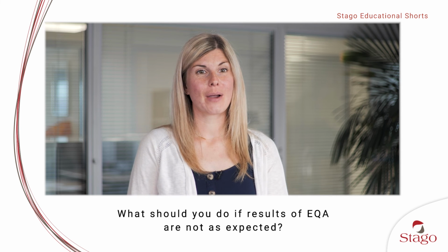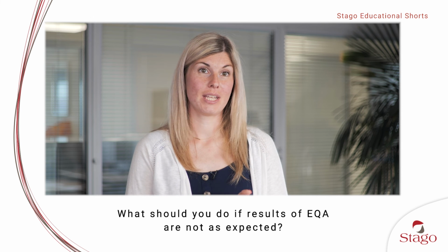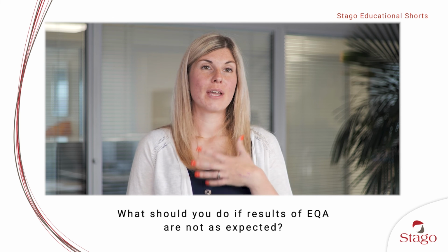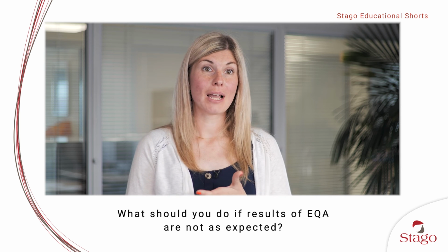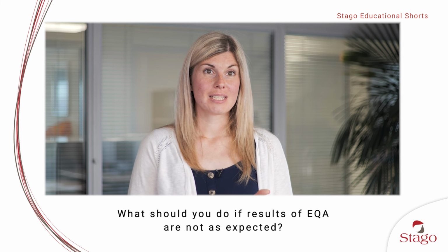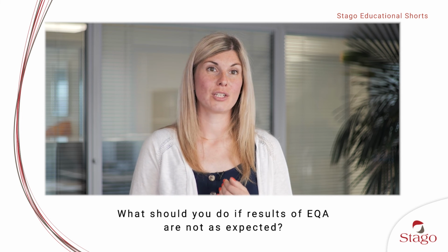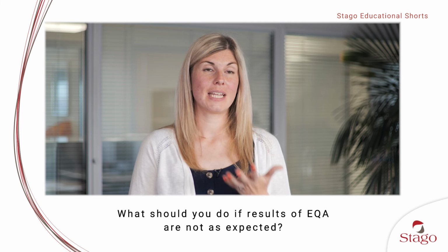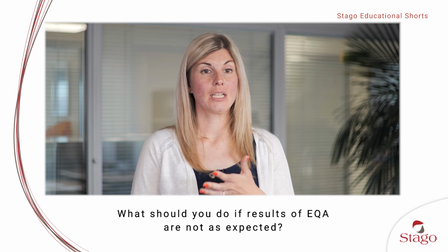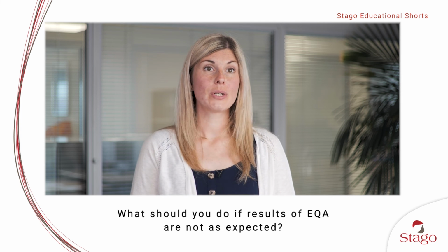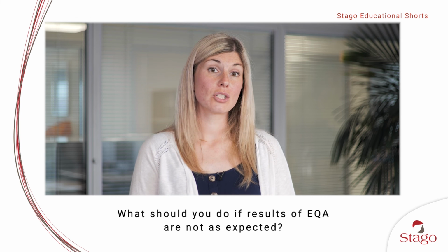Firstly, I would say get in contact with us here at UK NEQAS BC. Then we can always send a second sample out for you to test, and then we can give you further advice when you've sent your results back, whether any issues would have been user error, or whether you've got a calibration issue, or a quality control issue.